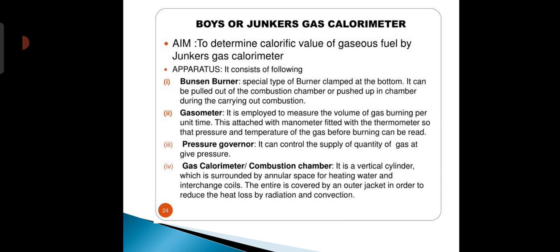Next, the gasometer. It is employed to measure the volume of gas burning per unit time. This is attached with a manometer fitted with thermometer so that pressure and temperature of gas before burning can be read.